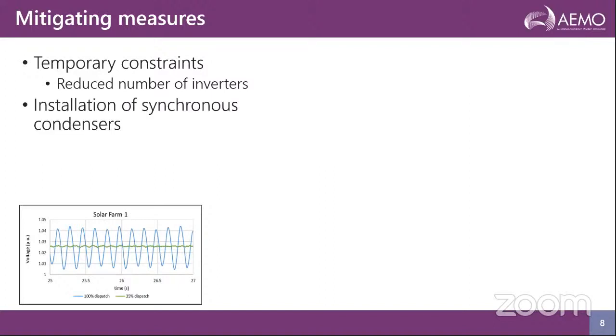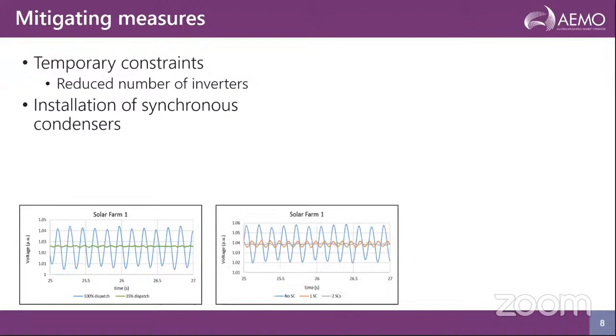Another solution is installation of synchronous condenser, which has been exercised by the South Australian transmission network service provider, which I will provide a little bit more detail on in the next slide. So this is, again, if you do not have any synchronous condenser, you could see post-fault or post-disturbance oscillation appearing in the system, and synchronous condenser can help to stabilize the oscillation by adding system strength to the network.